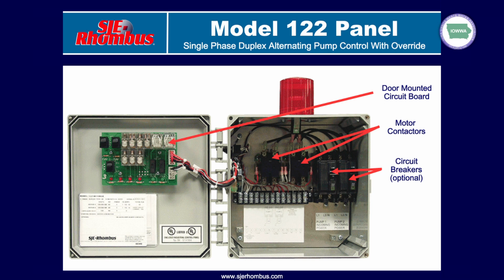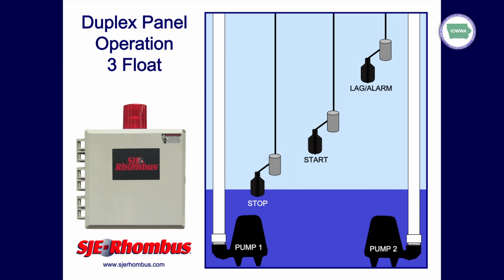All right. We're also going to talk a little bit about duplex control panels, where you're going to have 2 pumps that we're going to alternate between. And we're going to talk about the float setup when it comes to a duplex 2-pump setup, and how you use the floats and how you set them. We're still going to have a stop float. We're still going to have a start float. We're also going to have a lag/alarm float, like you see here.